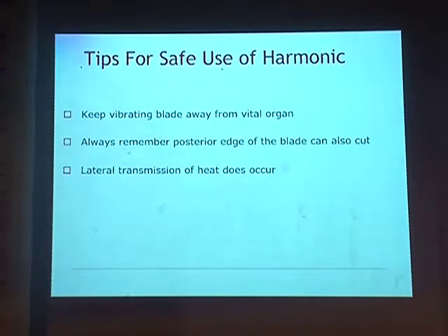Always remember the posterior edge of the blade can also cut. When you touch, I'll show some good videos, it just touches the blade and both sides cut. It's not only between the blade and the holding area; the other side also can cut. So the active blade should be away from any tissue which you do not want to cut. Those are the precautions you should take. And sometimes a slight lateral burn can happen. It goes up to 60 to 70 degrees Celsius in harmonic, but it can cause a slight lateral burn. So we should take care of these. Even if it's a mechanical energy, slight heat is generated because of vibrations.